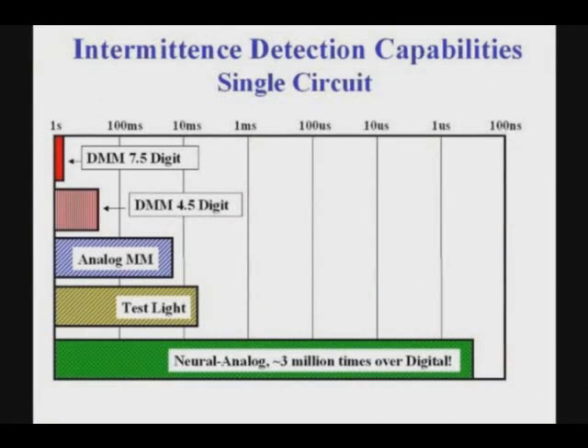This chart shows the intermittent detection capabilities of a variety of commonly used test and diagnostic devices when testing just a single circuit. As shown, digital devices, with all their measurement averaging employed to achieve phenomenal measurement accuracy, are practically blind to intermittent events.